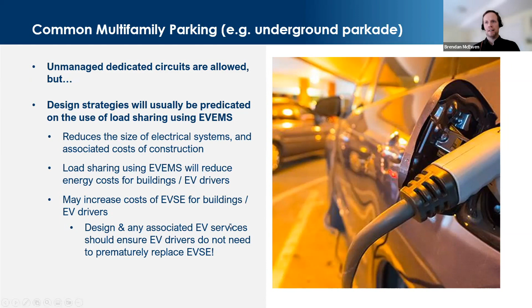The low cost strategies, which will be lowest cost for new construction as well as result in much lower power costs and utility impacts for occupants, are predicated on using load sharing, typically sharing across a branch circuit. That reduces the size of your electrical systems and energy costs. It means you'll need EV chargers compatible with that system rather than allowing households to adopt so-called dumb, unnetworked charging stations. So it makes sense to associate that building from the outset with a charging service provider that will provide good value, quality chargers at an attractive price, and other good quality services.